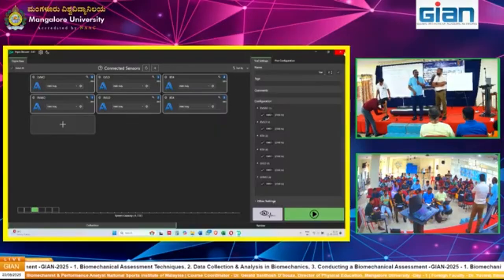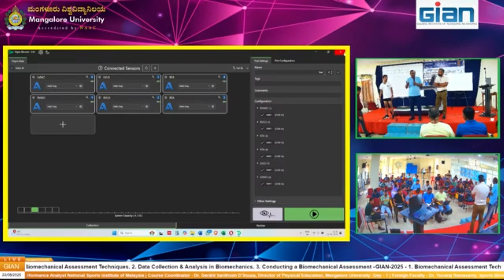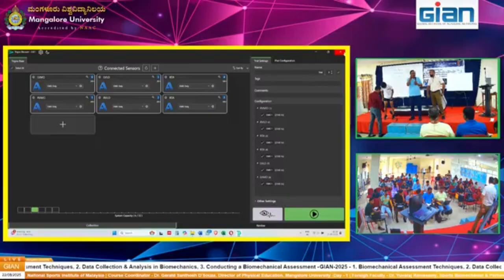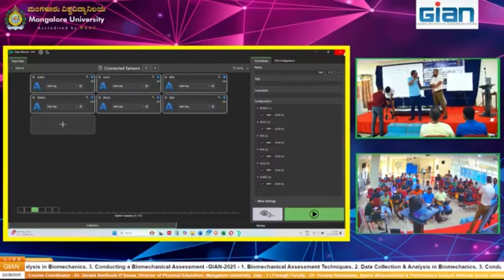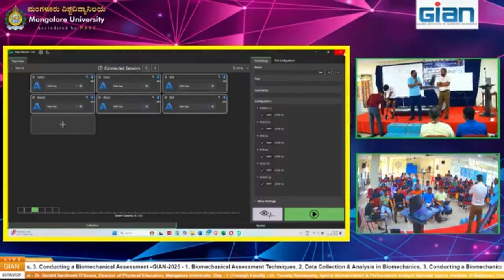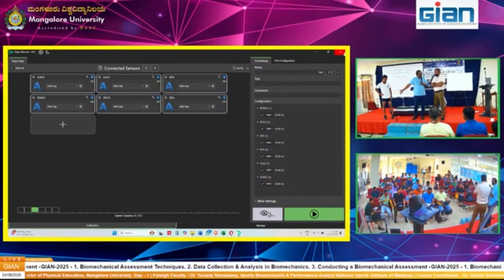The challenges we face are securing loose contact, sweat, and close proximity. Now this electrode has an advantage: both active and inactive electrodes are fixed and mounted in it, so that challenge is already overcome. What I used were button sensors, so those move. Now you have the technology of single-use adhesive tape, so you don't have to spread infections. Those challenges are overcome with this technology. This is all wireless as well, so that challenge is also overcome.